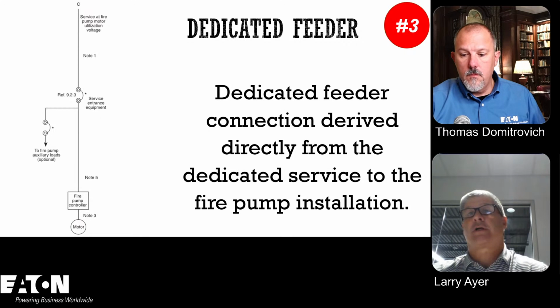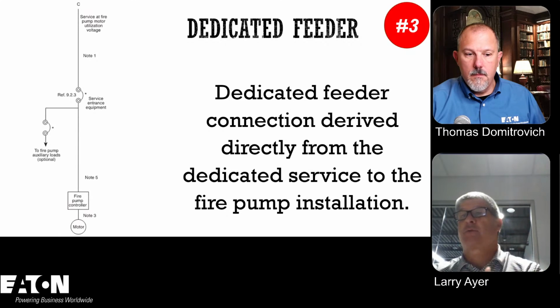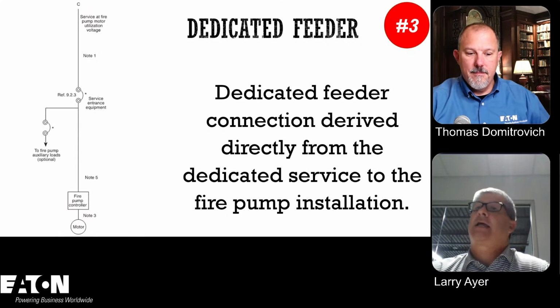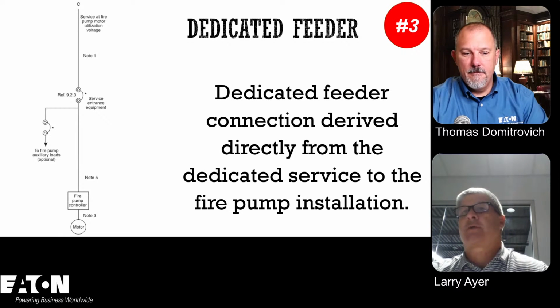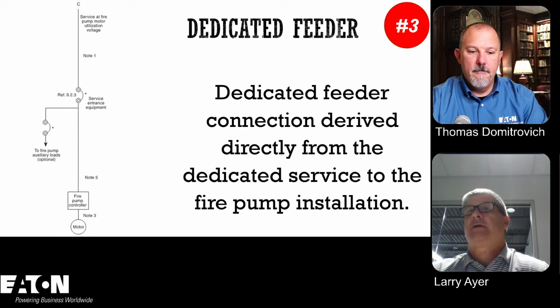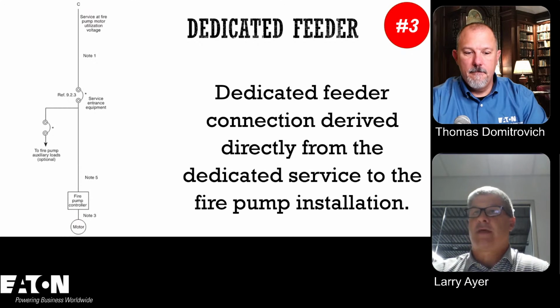So there's no overcurrent protection, so those are considered service conductors. If you were to do this option, number 3, you would tap off the service. You could either tap off the switchboard and set a disconnect next to the service entrance, or the service switchboard, or somewhere next to the service, or you could come from the transformer and set a disconnect. Once you set that disconnect overcurrent device, then that becomes a feeder, and then you run that to your fire pump controller.